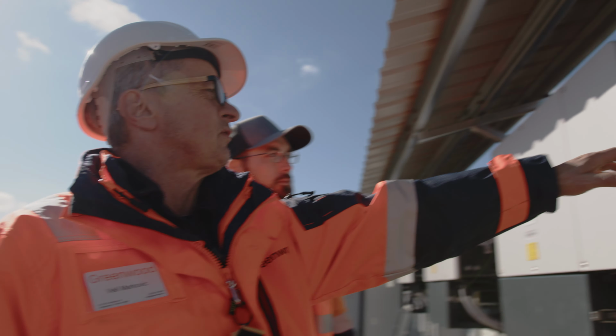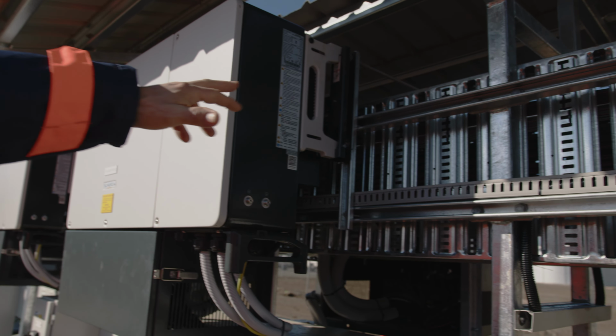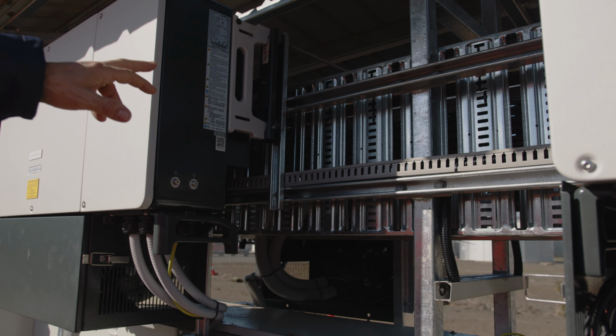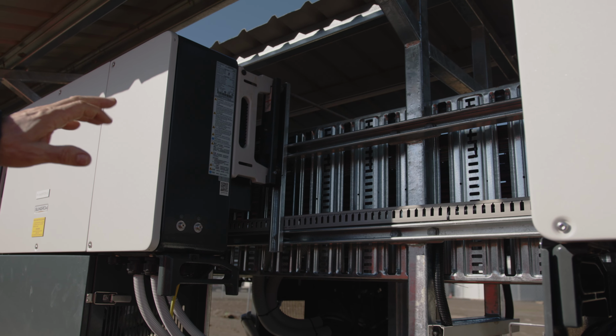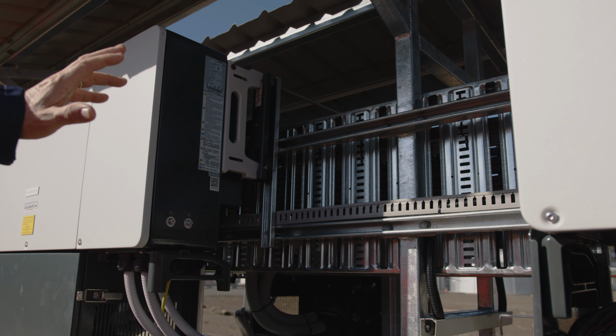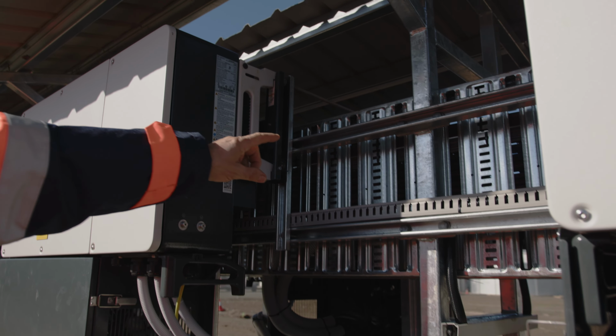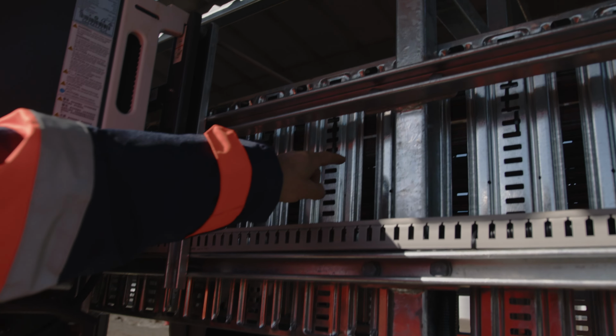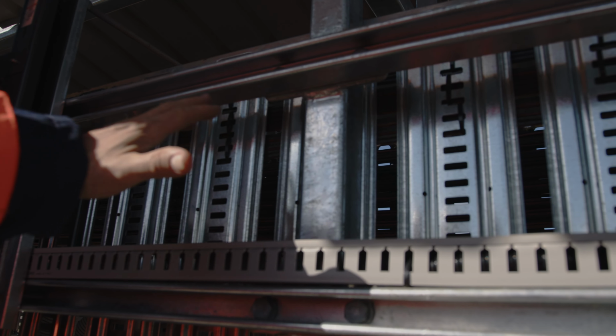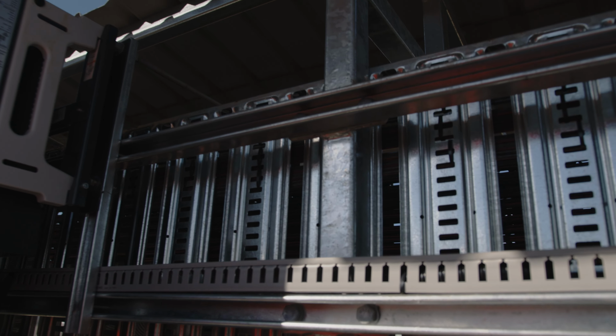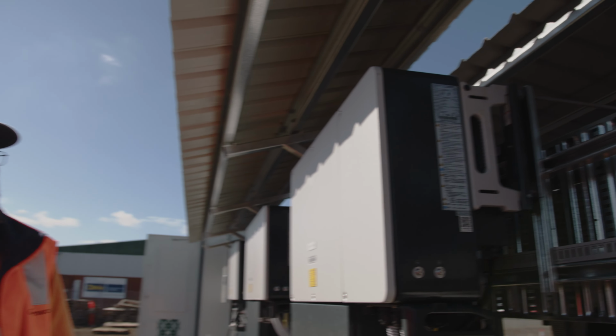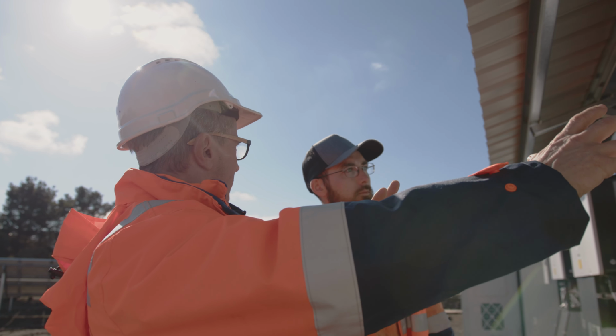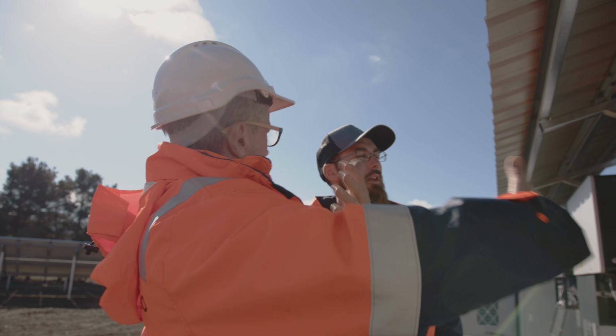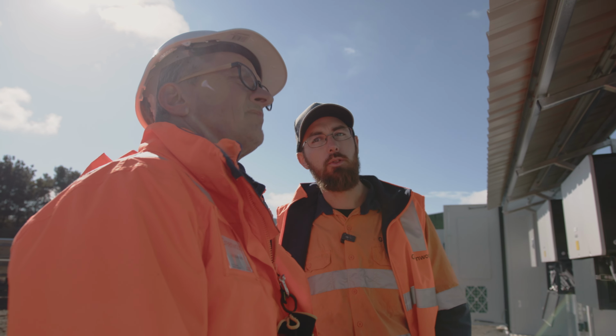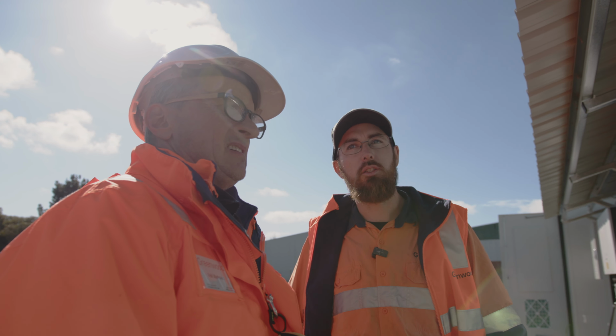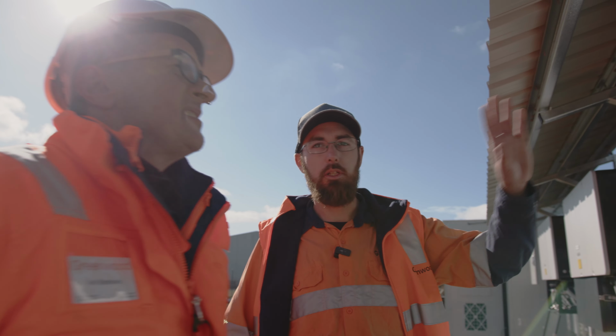And I noticed too, we've got some, I'd say that's 450 cable. I'm really bad with the width. Is that 600? It's 600, yeah. So 600 cable tray, accommodated on both sides of the inverter station. And if you look closely, you can see the twin 6mm DC cable, all neatly configured, running in between there, and it's almost as if one of the cable trays is being used as a lid. They're both lids, aren't they? Yeah, by facing the trays inwards, it does offer a bit more protection to the cables, which houses them securely. On a site such as this, we're not too worried about having to have that completely covered for people touching it.